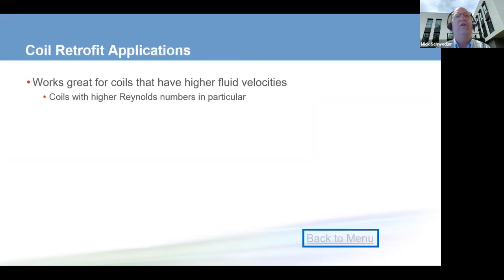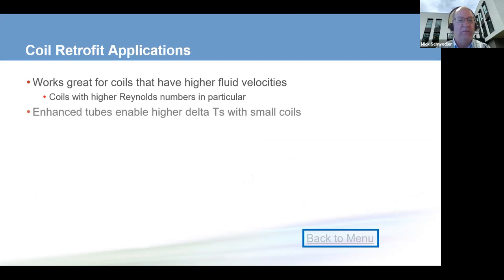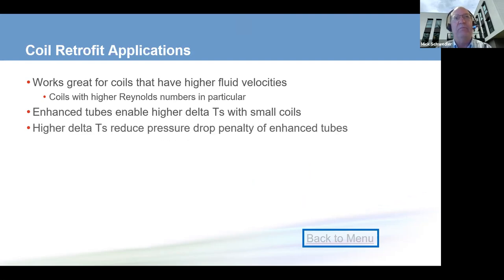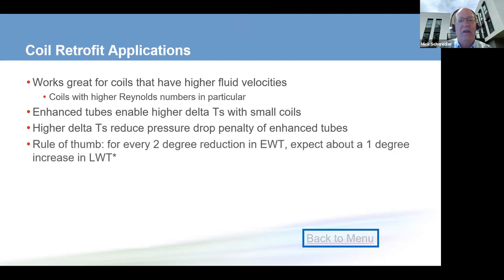So in retrofit applications, coils with high Reynolds numbers work well, and also on the smaller coils, enhancing the tubes. There is a pressure drop for those enhanced tubes, but when you have higher delta Ts, you reduce the flow rates and reduce the overall pressure drop. A rule of thumb, which I really hesitate to tell you because they never always work, if that makes sense: for every 2 degrees you give a coil colder water, the return water temperature will come back about 1 degree warmer. But don't use this rule of thumb on an existing coil. Work with the manufacturer to reselect that coil and find out if it works for the particular coils that you have.